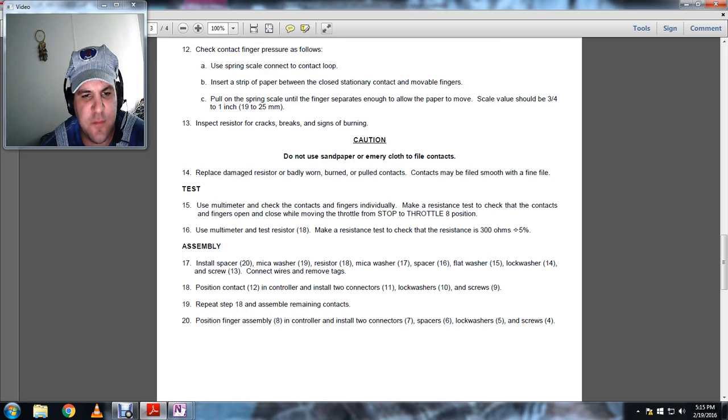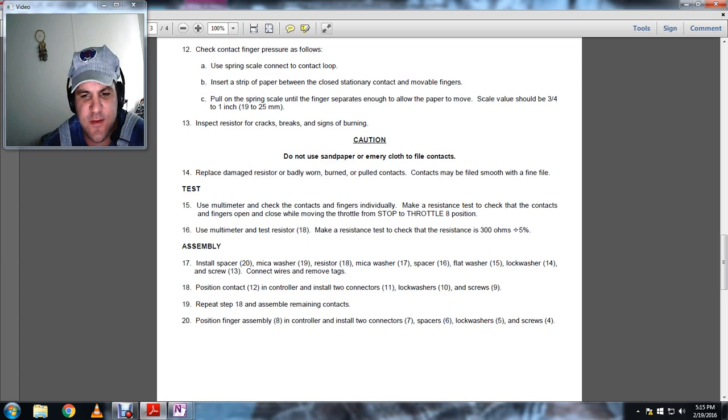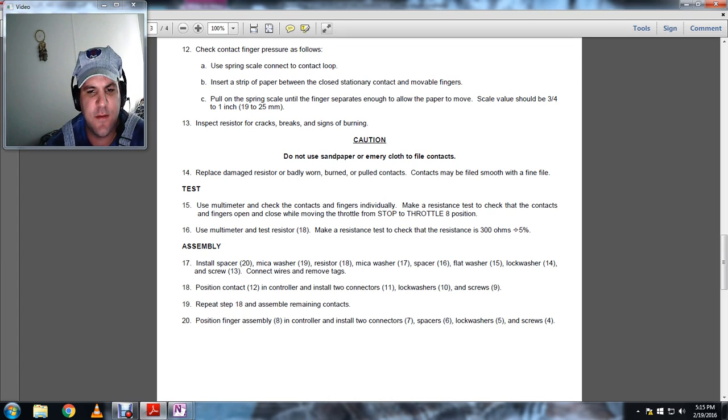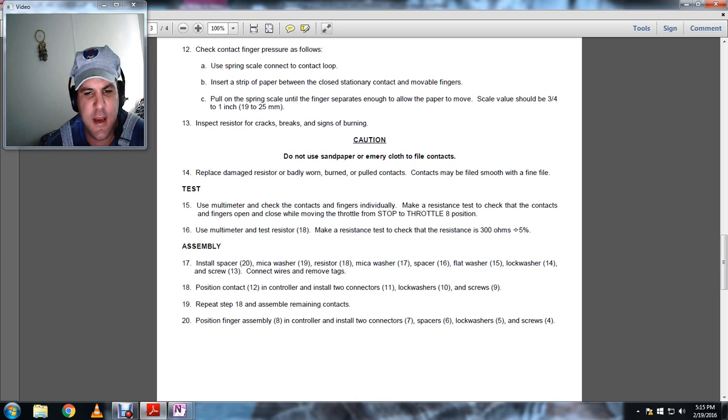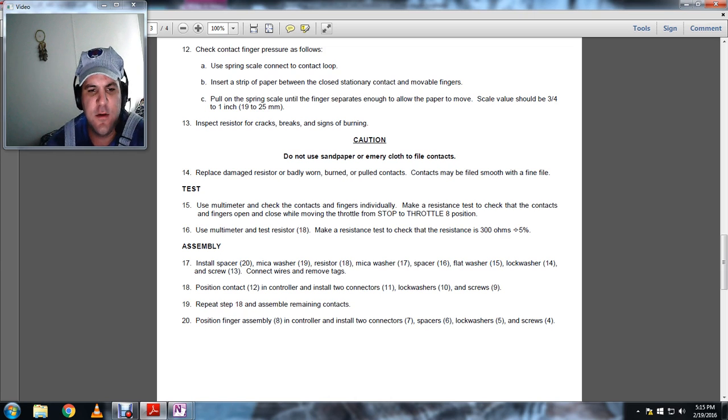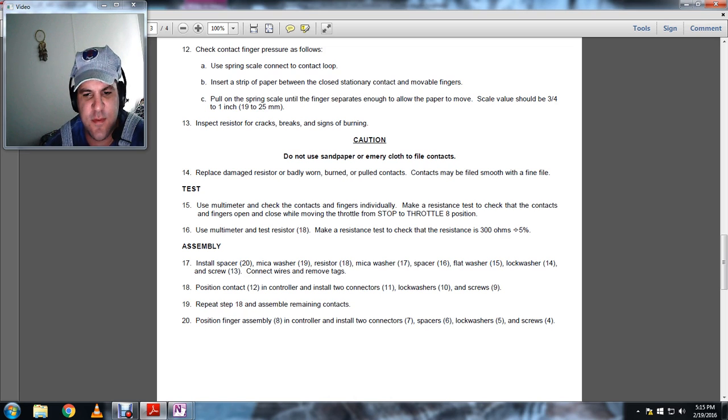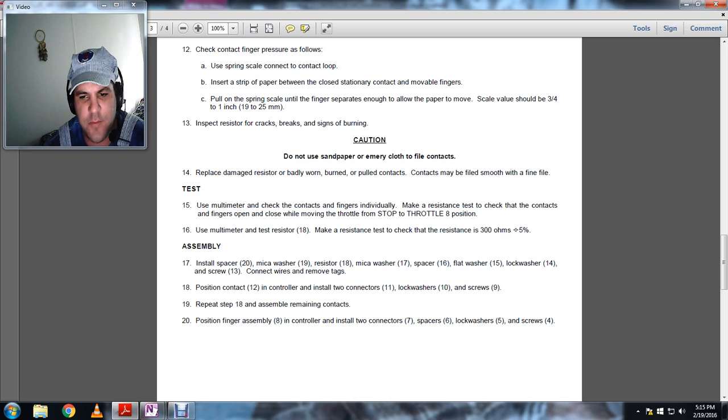Test. Use multimeter. Check for contact fingers. Individually make a resistance test to check if the contacts and fingers open and close the moving of the throttle. from STOP to THROTTLE 8 position. Use a multimeter to test resistor. Make the resistance test to check the resistance at 300 ohms, plus or minus 5%.